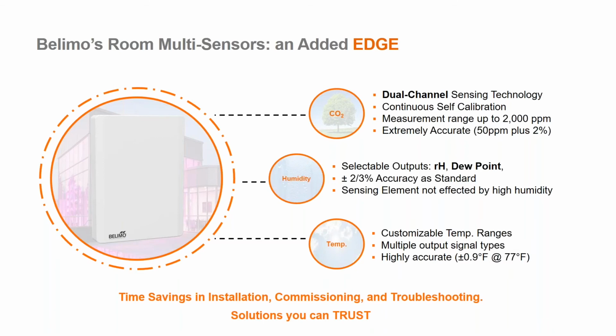On the humidity side, you have a selectable output between relative humidity and dew point, both of which can be monitored through the NFC app as well. These are plus or minus 2 or 3%, depending on which part number you choose. Temperature-wise, fully customizable temperature range on this active model through NFC, and again selectable outputs: 0 to 5 volt, 10 volt, 2 to 10, and MP bus, all through this NFC app.